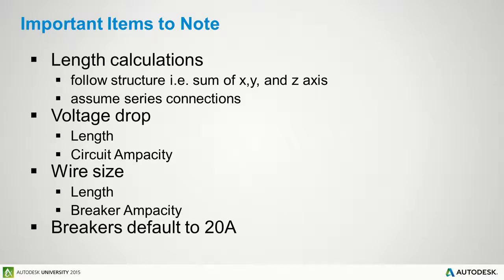Revit assumes series connections, which we've talked about, which will get us in trouble regarding our wire sizes. So a lot of times I like to use the length for a lot of my motors and such, do some loose voltage drop calculations or do some takeoffs for SKM between my panels, rather than having to actually get the ruler out or draw the poly lines and take the length off. I can create a schedule with all of my panels and the length that connects them, because I know that that panel only has one thing downstream. So it improves our SKM short circuit calculations.